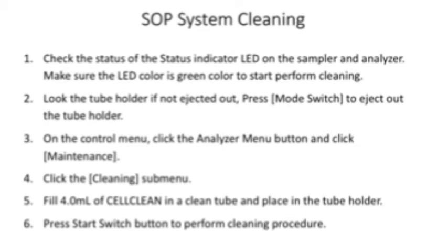And next, on the control menu, click the analyzer menu button and click maintenance. After that, click the cleaning submenu. Fill 4 ml of CELLCLEAN in the clean tube and place it in the tube holder. Press the start switch button to perform the cleaning procedure.